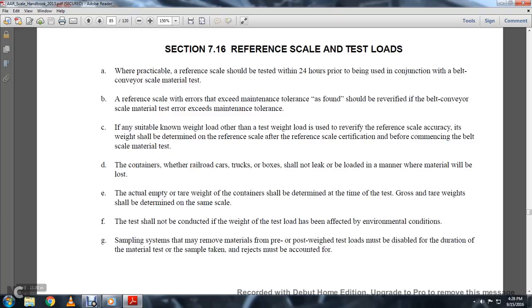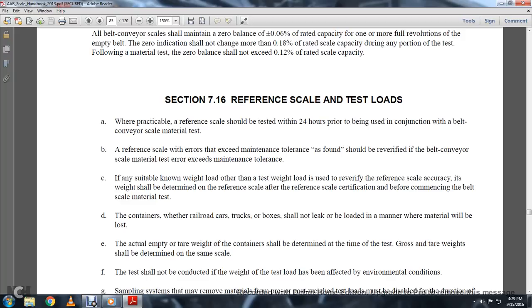Section 716, Reference Scale and Test Load. When practicable, the reference scale should be tested within 24 hours prior to its use in conjunction with the belt conveyor scale material test. A reference scale with errors exceeding maintenance tolerance should be re-verified. If a suitable known-weight load other than the test weight load is used to verify the reference scale accuracy, the weight shall be determined by the reference scale. After reference scale certification, containers—whether railway cars, trucks, or boxes—shall not leak or lose material. The gross and tare weight shall be determined by the same scale.